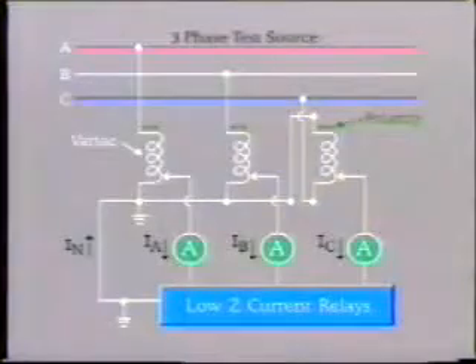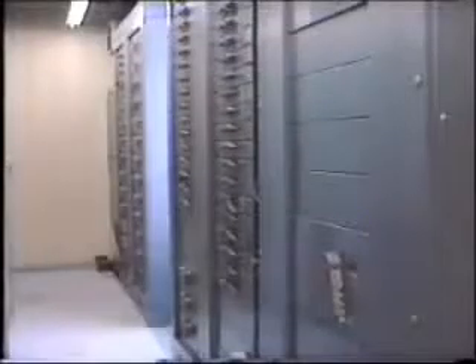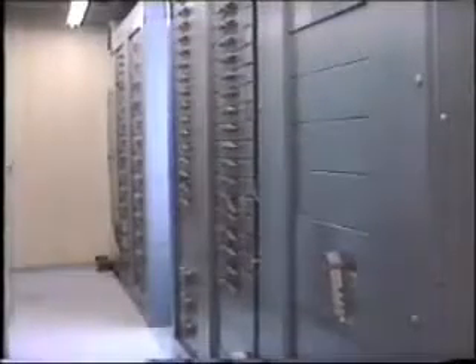The variac, ammeter, and the relay may have been put out of commission. Speaking of voltage sources, here is a very important testing rule. Never use bus pots, VTs, as a test source unless absolutely necessary. If station service is available, use that.